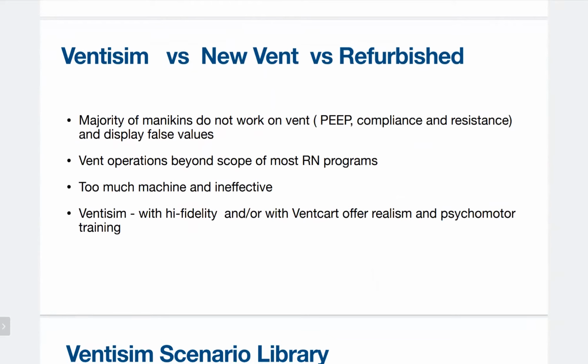But before we get to that, we just wanted to talk a little bit about vent training in your simulation lab. And as many of you have probably found, the majority of mannequins, unless you're spending over $100,000, will not accurately work on a ventilator. And this is for a couple of reasons. The lungs aren't designed for that. So they aren't designed to hold PEEP, nor are they designed to have accurate compliance and resistance. So in many cases, you could buy a $50,000 adapter to do that, or get an expensive mannequin. But a lot of people are looking at refurbished or new ventilators, but they will not provide accurate readings or be able to run accurate scenarios and give you realistic vent settings with the majority of mannequins out there. So in many ways, too much machine and not needed. So this is a cost-effective solution.